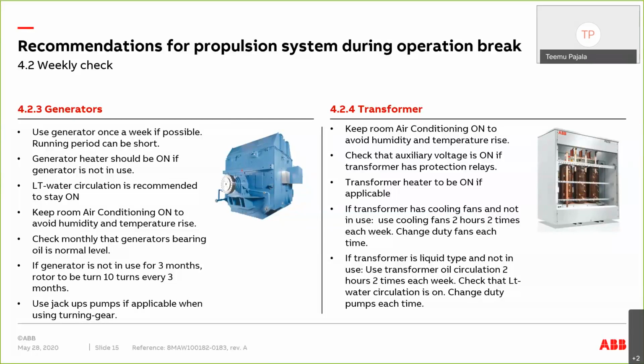Then change the duty fans each time so that all the fans are used on a weekly basis. And if it's a liquid cooled transformer, then the same needs to be done for the cooling pumps. And when the cooling pumps have been used, the LT water circulation should also be on.